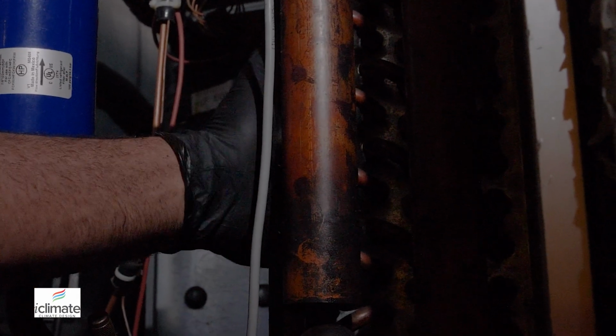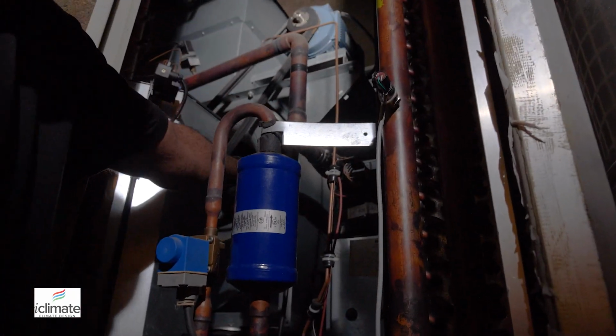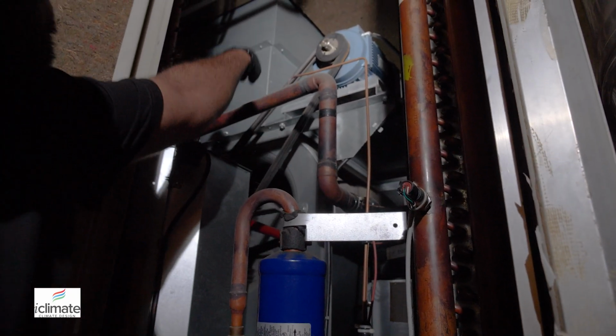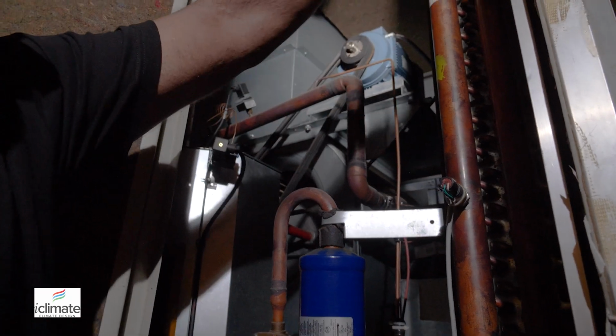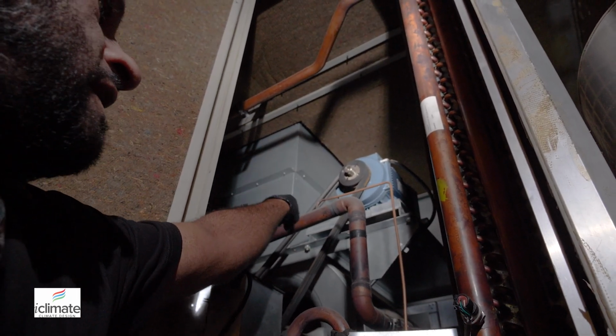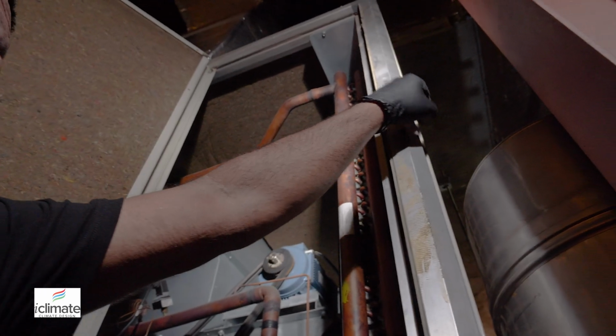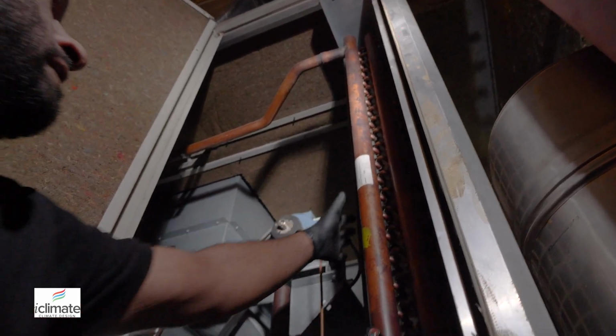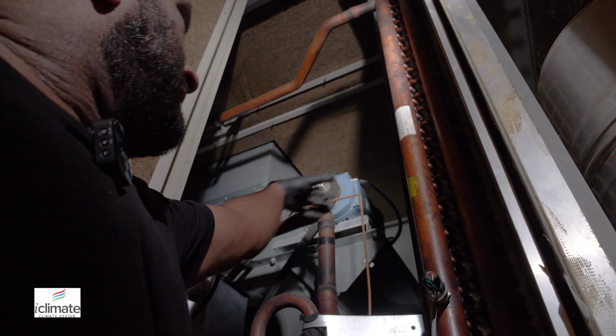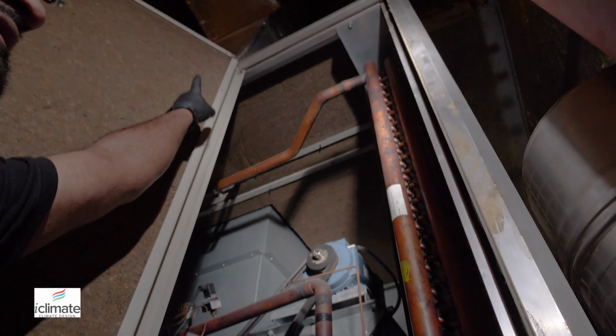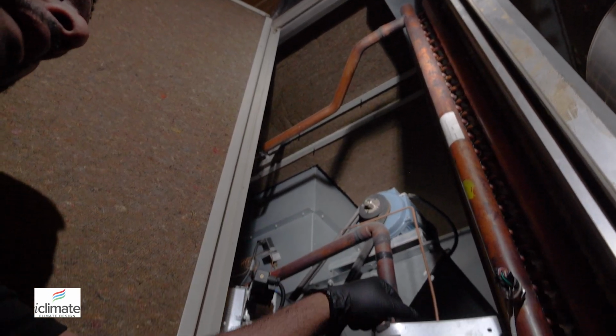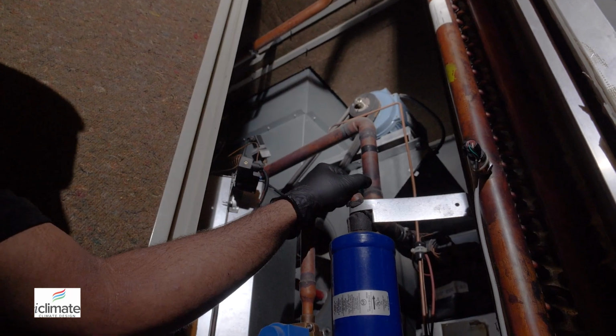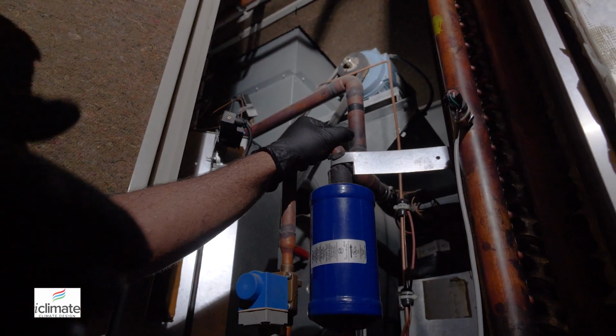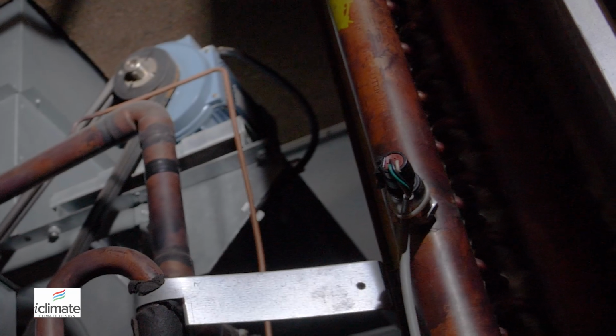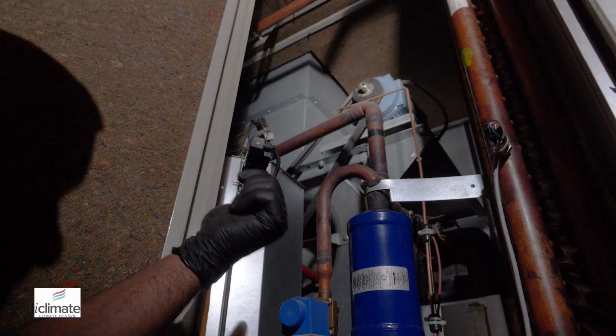This is our condenser coil here with the distributors on each side. So the condenser is inside, right? What's here? This very large fan, belt driven with a duct on it. So what happens is the air is pulled when the fan moves and rotates. It takes air from the other side of the coil, which is essentially the outside, because this is a vented chiller. It draws the fresh air across the condenser into this compartment, takes it up and out, and then discharges it through the discharge ductwork at another remote location not too far away. The air that's discharged and the air that's taken in are quite a distance apart, so there's no cross contamination of the air or short cycling, which would make the chiller overheat.